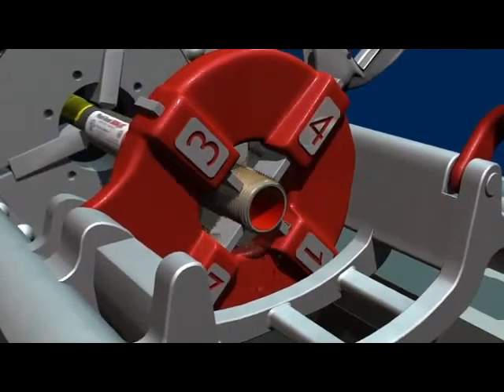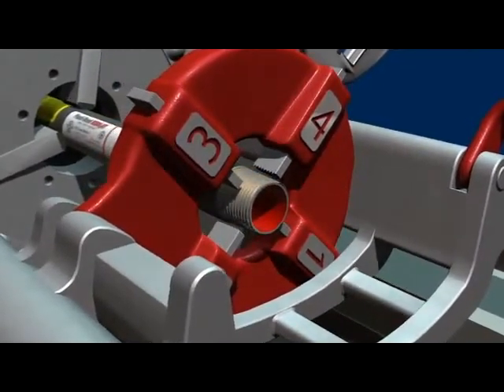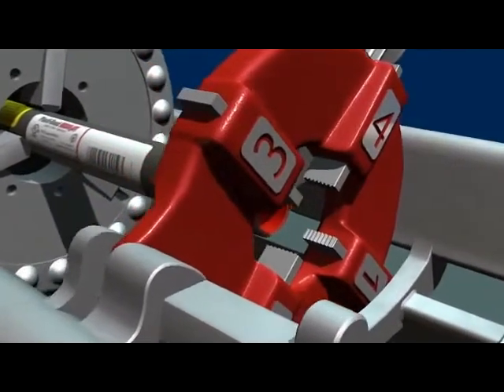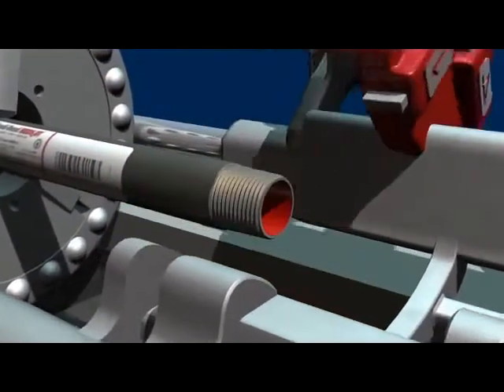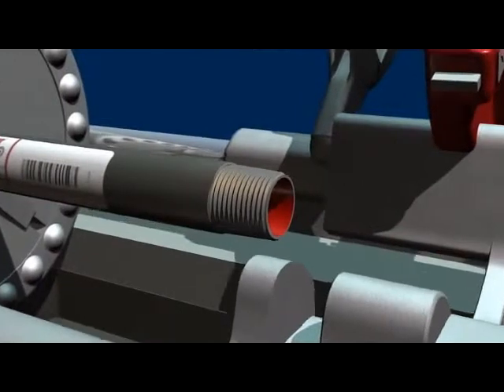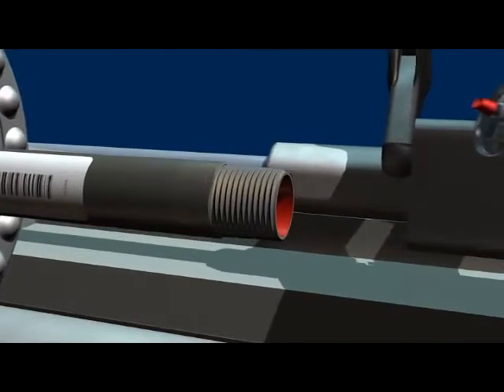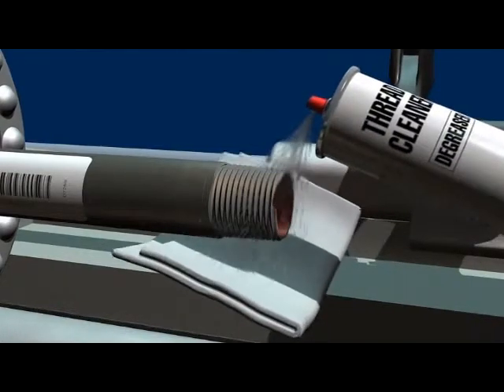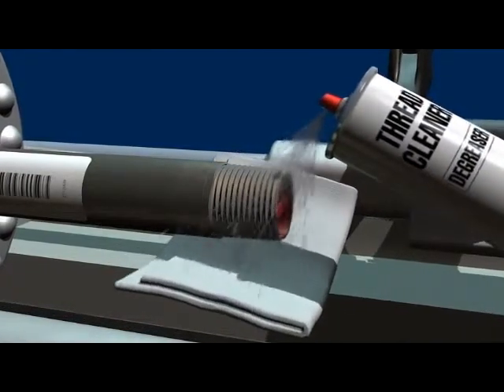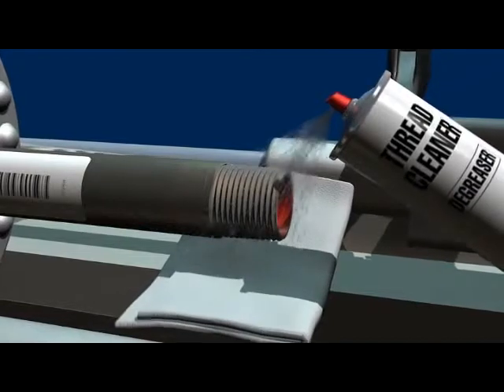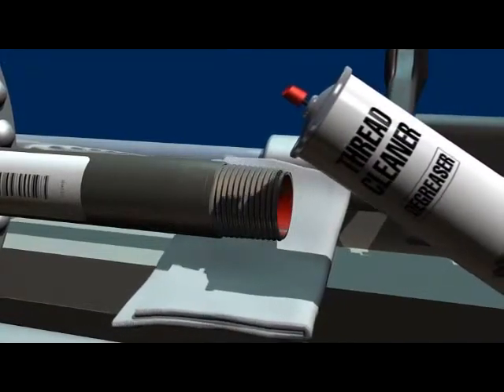Use a good quality thread cutting oil to flush away the metal and PVC chips. After threading, use a degreasing spray to thoroughly clean the threads and the interior of the pipe. Use care not to contaminate the cutting oil with degreasing spray. As a safety precaution, never clean the pipe while it is still spinning in the power drive.